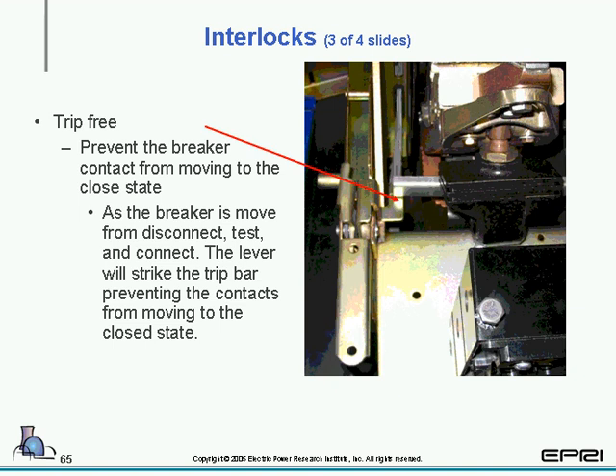The next one we have is the trip-free, which prevents the breaker contact from moving to the closed state. As the breaker moves from the disconnect, test, or connect position, the lever will strike the tripper bar. This particular lever will strike this tripper bar and will prevent the contacts from moving to the closed state. And that's a definition of trip-free, when the contacts never move towards the closed state.